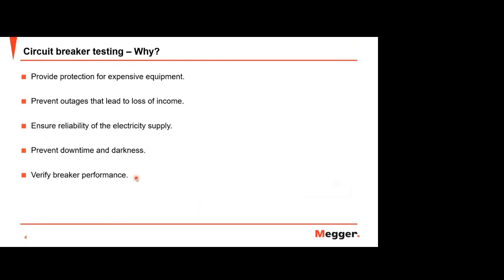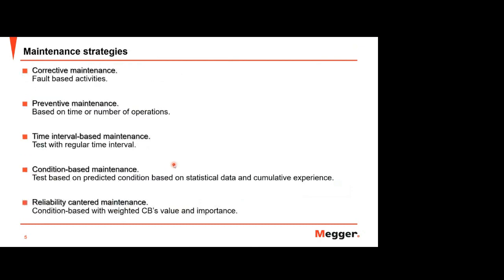So after you get a new breaker, or after you have a fault on your system, you can check and verify the breaker performance with circuit breaker testing. And let's talk about the maintenance strategies. There are many methods used to maintain your system, especially for circuit breakers, such as corrective maintenance.